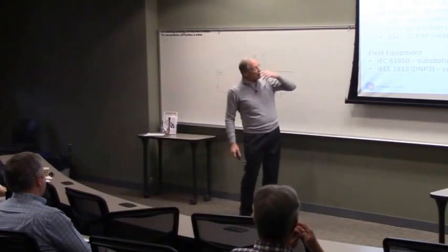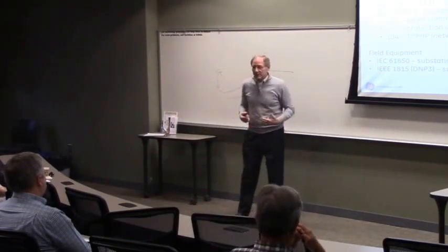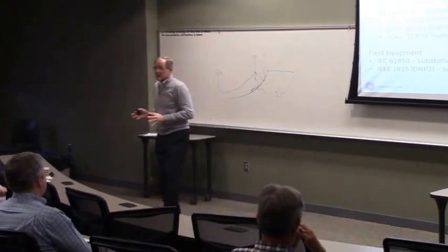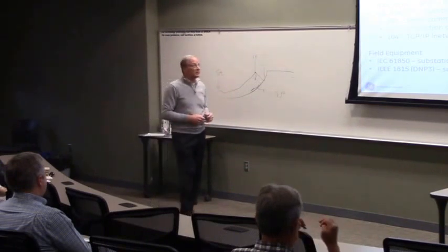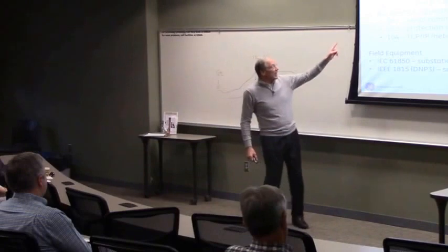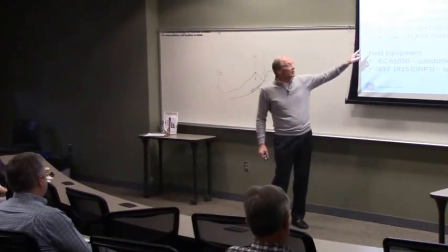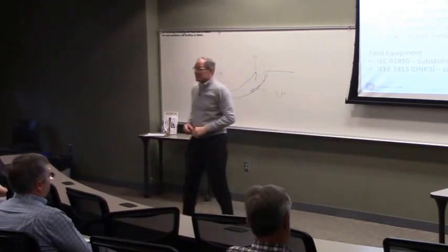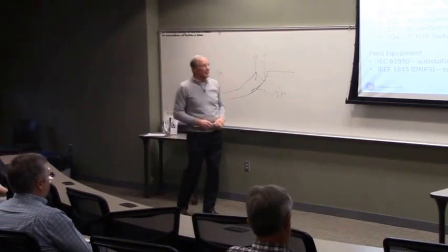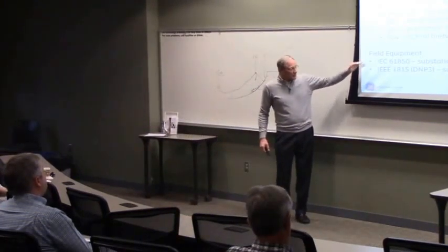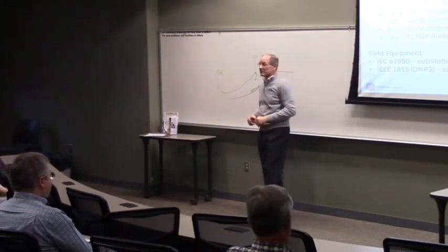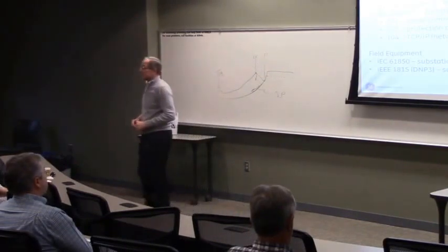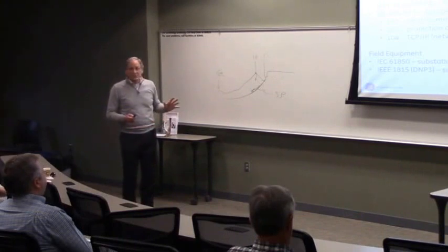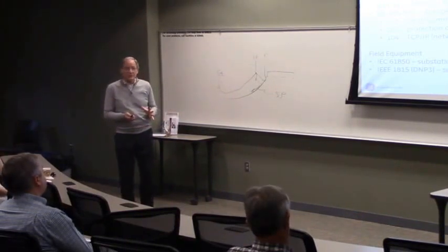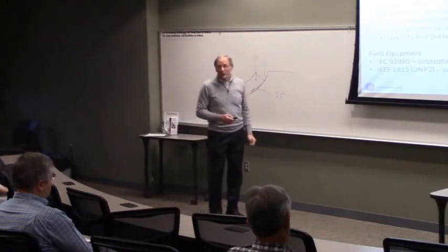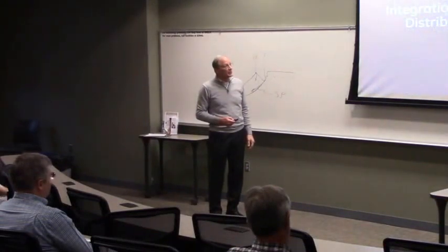So DNP3 is used in North America. If it's a European supplier, like ABB, Siemens, or Schneider, they don't use DNP3 and aren't that familiar with it, which is kind of a red flag in North America. What they're more used to is IEC 870-5, 101 for serial communications and 104 for network communications, because that's the predominant SCADA protocol outside North America, in Europe. And then in the substation in the field, we'll see DNP3 or IEC 61850, which is truly the worldwide standard in substation automation, communications, and architecture. What's nice is we converge to a very small number of choices. So it's much easier today to determine what you should use, much easier than before.